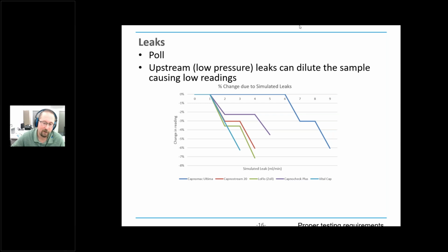Now this blue line over here actually is an anesthesia device. And remember, anesthesia devices are much higher flow rates, so they're at 200, 250. And so they're not as affected by little leaks, but 6 milliliters out of 200 is not a very big percentage. So even a small leak in that scenario can cause your numbers to be off.